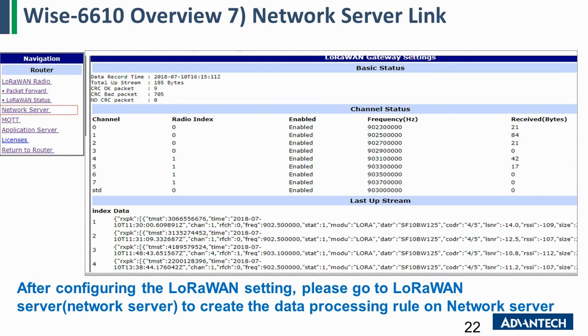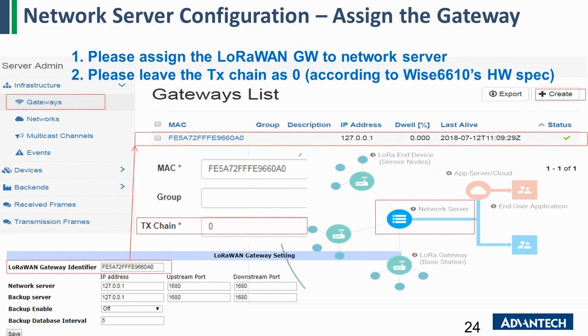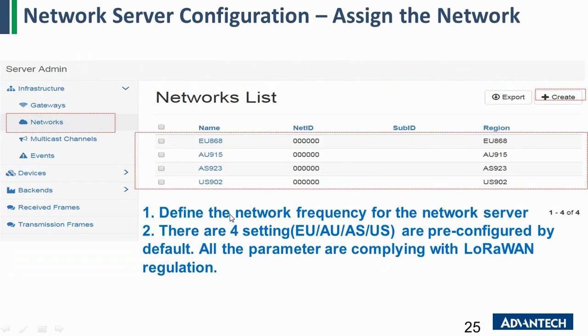After all settings have been configured, let's go to the network server path. In this section, we will show you how to do the configuration for the network server function on our WISE gateway. The network server is a software function, so you have to define what kind of information it needs to process. Input the gateway so the network server knows which gateway's data to handle. We will leave the gateway TX channel at zero. For network frequency, we have four default settings for different countries, so you don't need to configure the frequency manually.